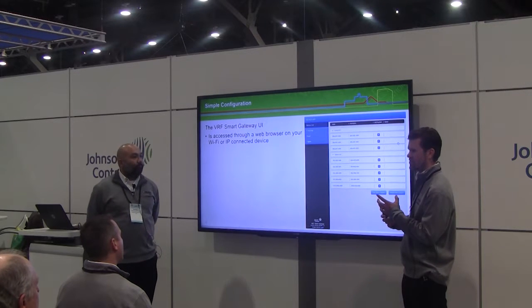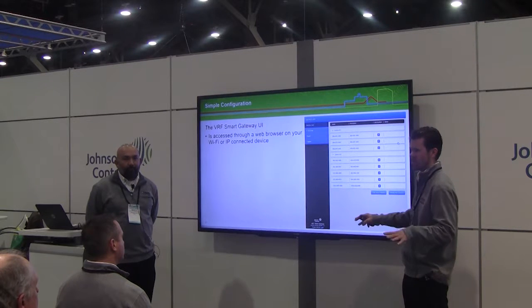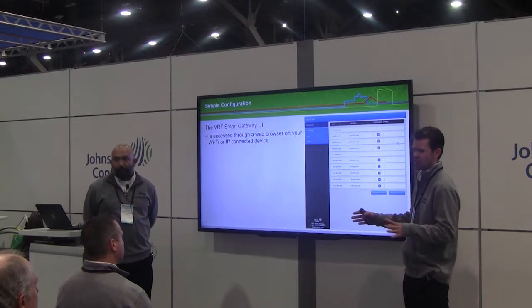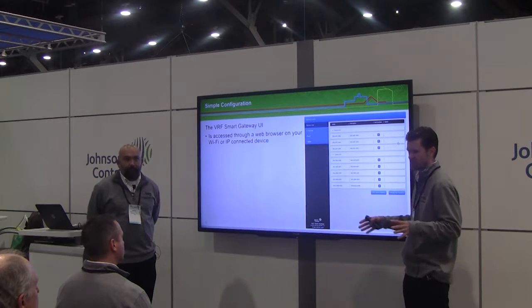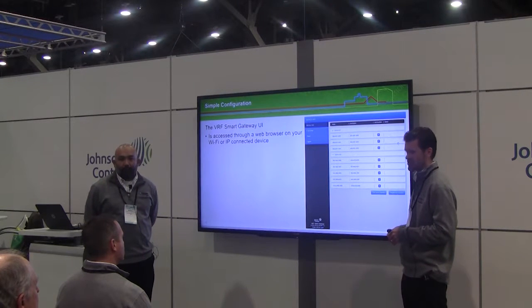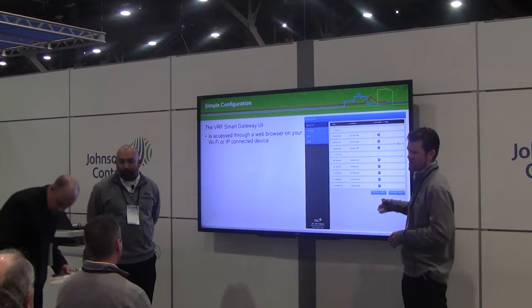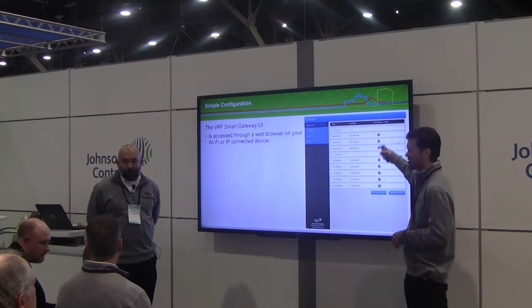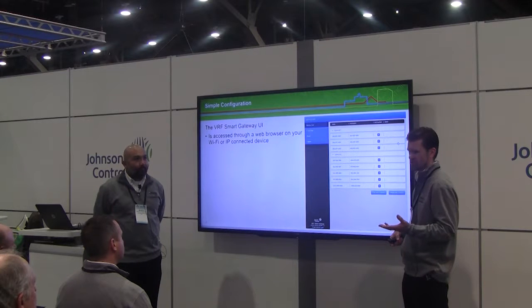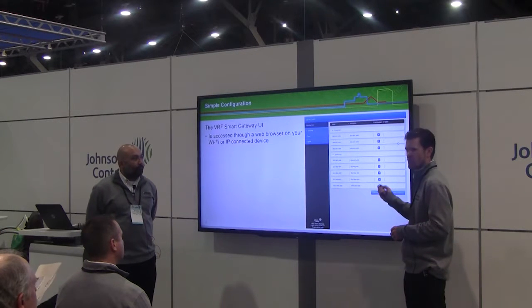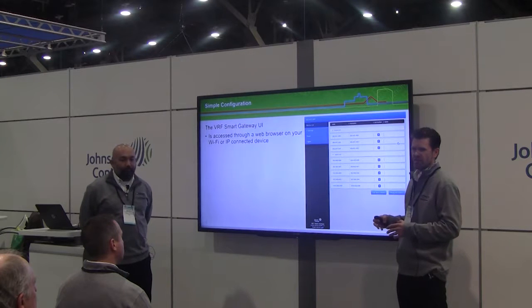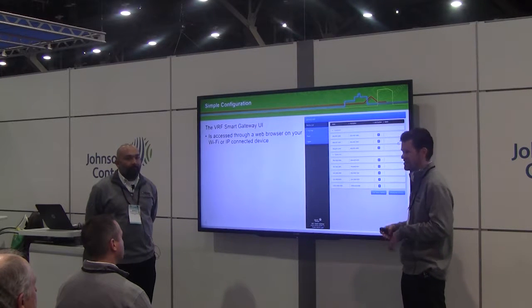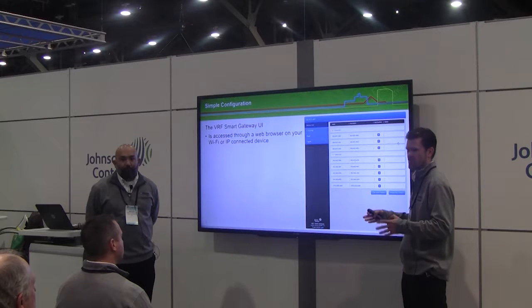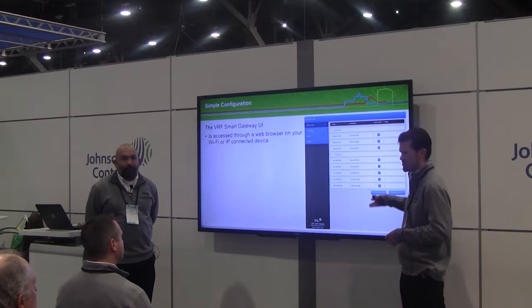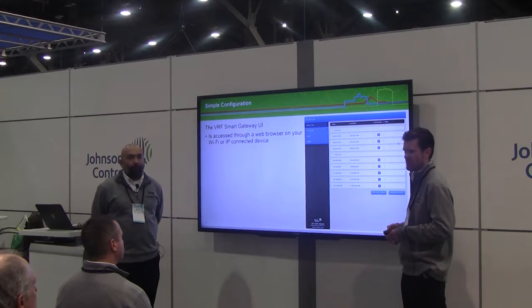When you connect the VRF Smart Gateway to your VRF system, it automatically goes out and discovers your units. So you don't have to worry about how the addressing scheme is set up. The gateway knows how to go find those units. And by the time you've had a chance to log into the user interface, you'll already see your list of indoor units and outdoor units. So it becomes a tool to provide an initial sanity check to make sure that your indoor units and outdoor units are communicating on the network, and you get a nice list displayed almost immediately.